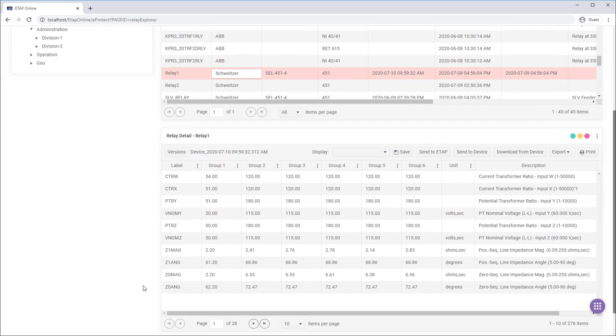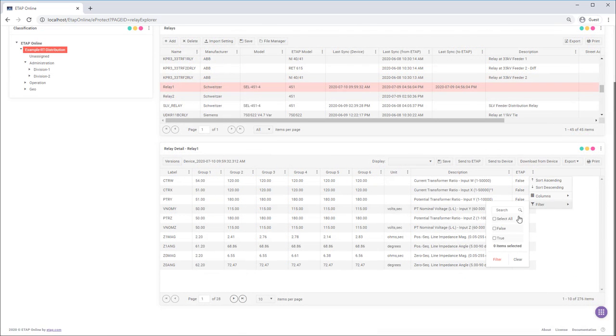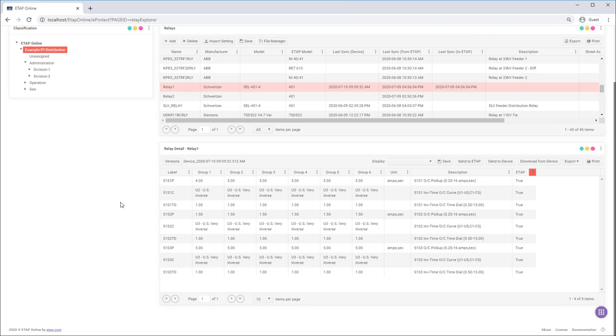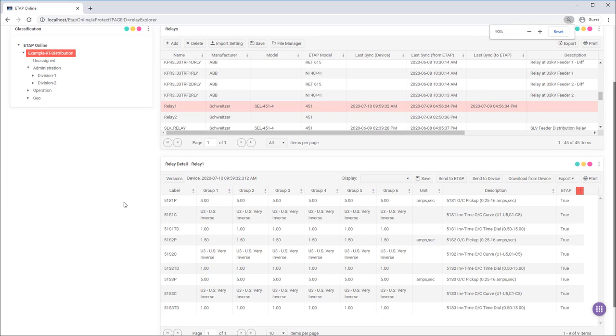Selecting Relay 1 allows me to view all the settings of this relay. I can see the labels and description as provided by the vendor. There is also a filter for ETAP that I can set to true, which filters the properties to the ones that are used by ETAP for protection and coordination studies.